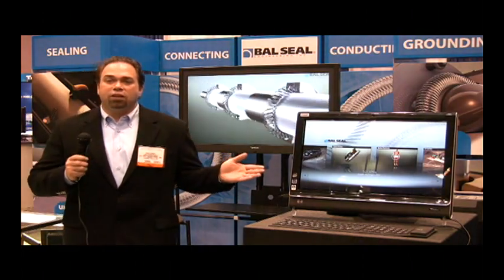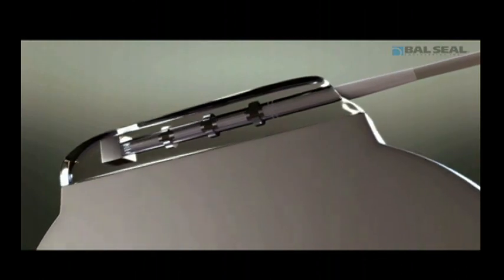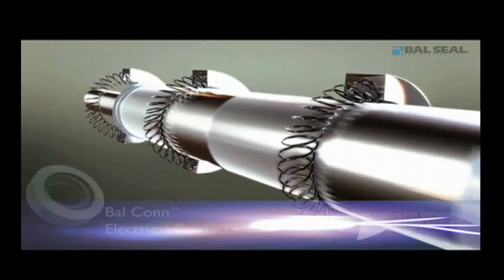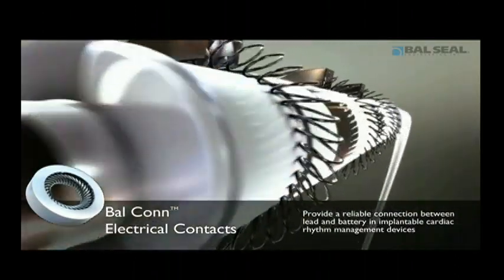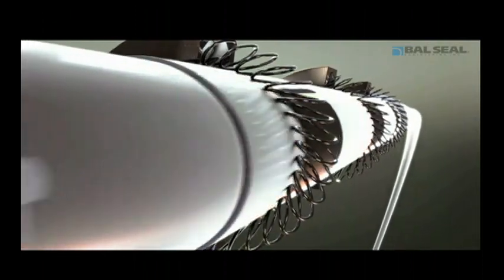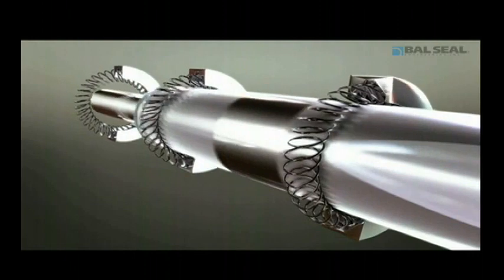Now let's take a look at some applications. In this first animation, we show a cardiac therapy application. Bal Conn technology is used in cardiac rhythm management for both pacing and defibrillation. This configuration shows three Bal Conns in series. This typical IS-4 design would be accompanied by a set screw to secure the lead. The tool-less connection provided in this system reduces time of surgery and potential complications associated with multiple set screws.